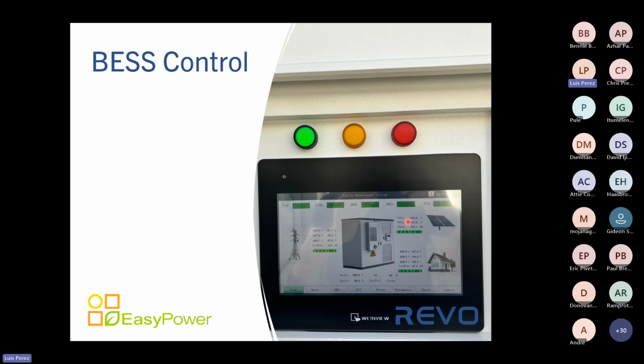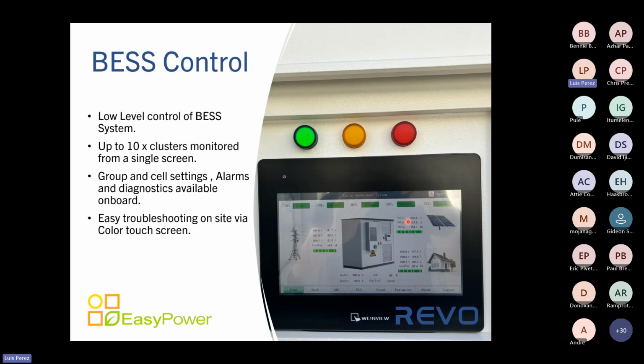Some batteries on the market, you actually cannot do that - they are black boxes. You can see SOC and voltage, but you cannot really drill down into every single cell temperature and voltage. Our system is an open type of system. We have low level control on site down to every single parameter that the BCMU can actually use for controlling and protecting the battery.